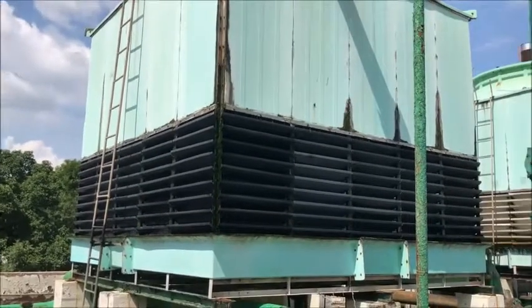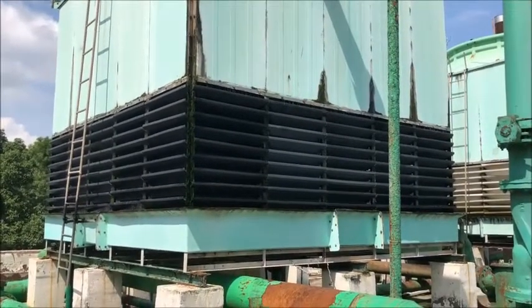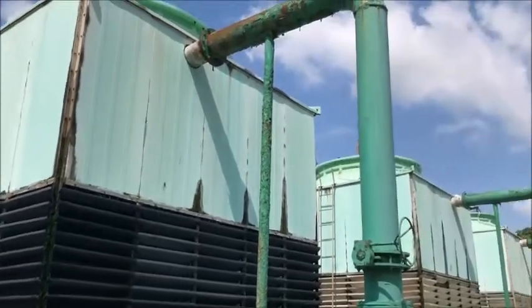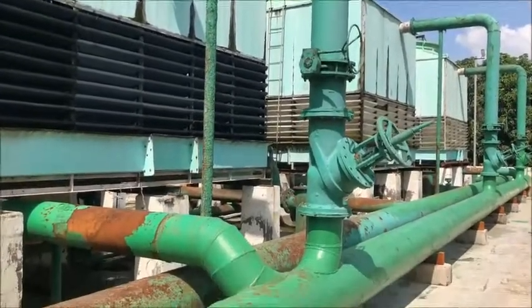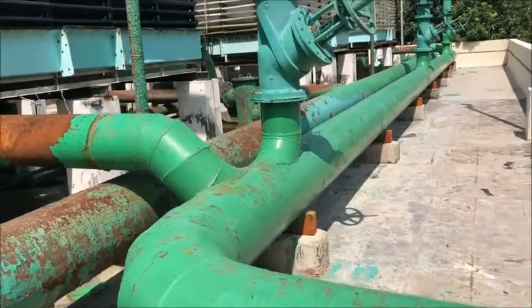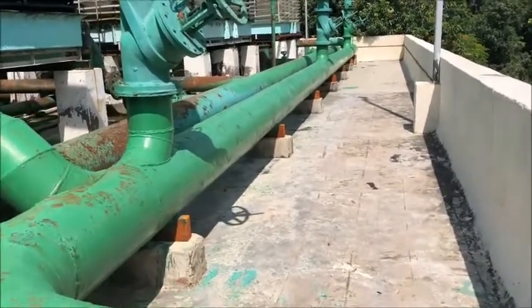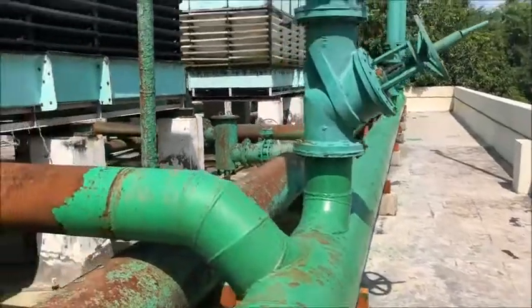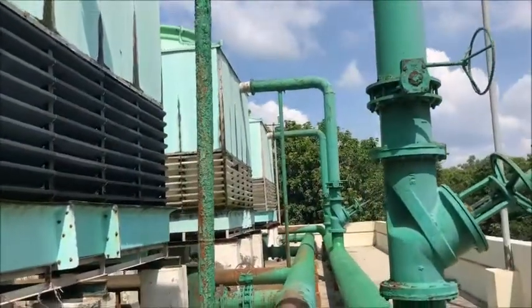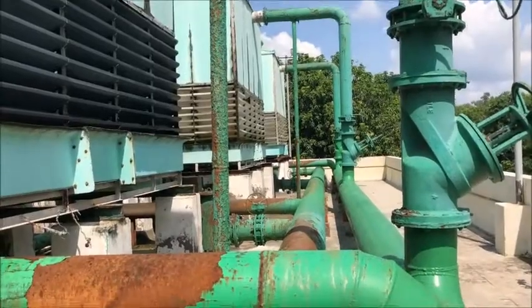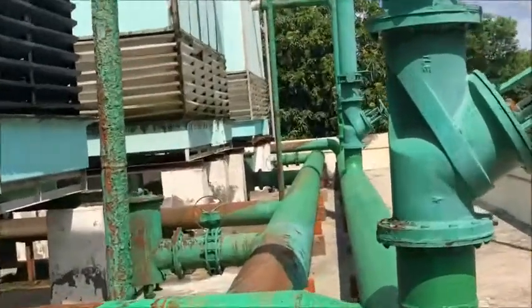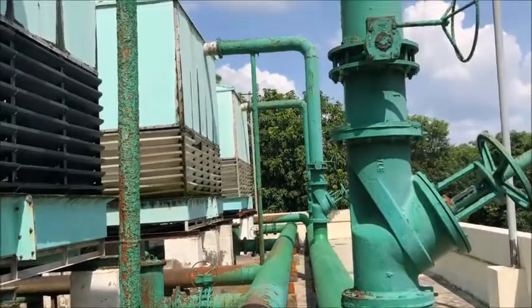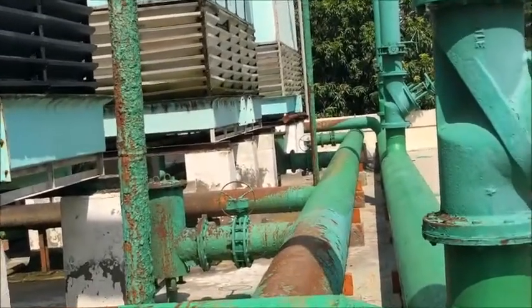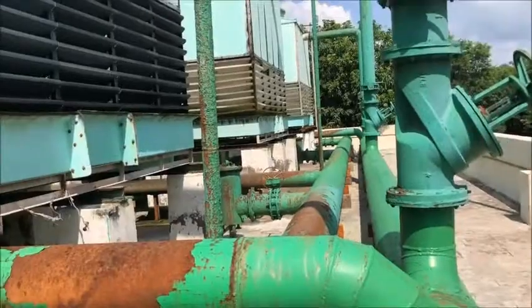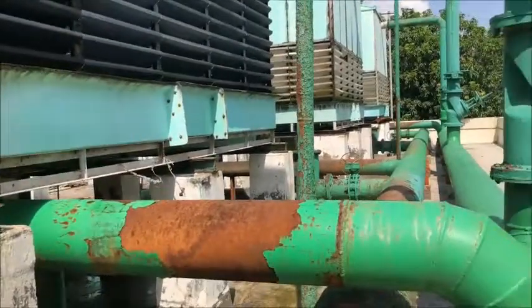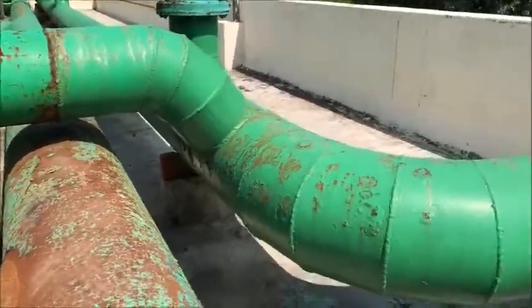Now I will go to the cooling tower. You can see these are the cooling towers. So for our 4 chillers, we have installed 5 cooling towers. These cooling towers are induced draft counterflow cooling towers. This pipeline that I'm showing you is coming from the condenser of the chiller. This is a balancing valve, and above the balancing valve there is a butterfly valve. Through this balancing valve, the flow of water across each cooling tower is manually regulated.